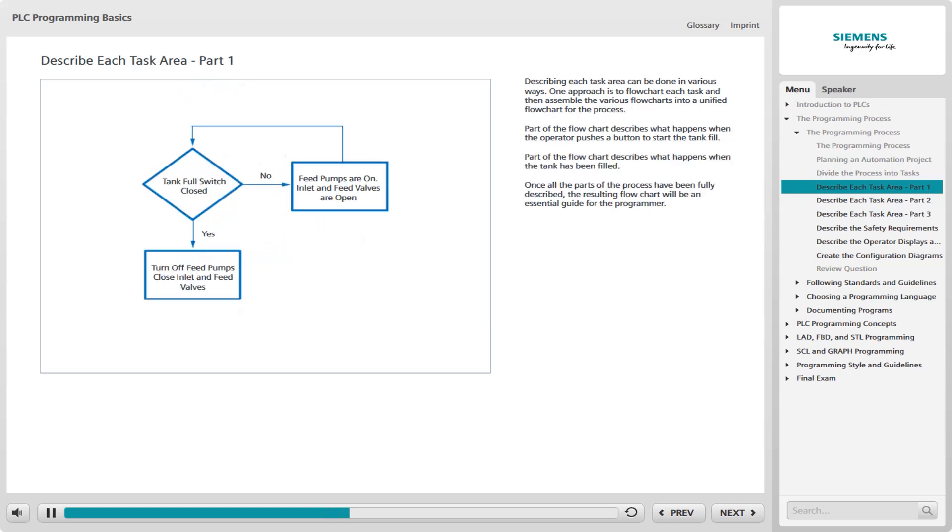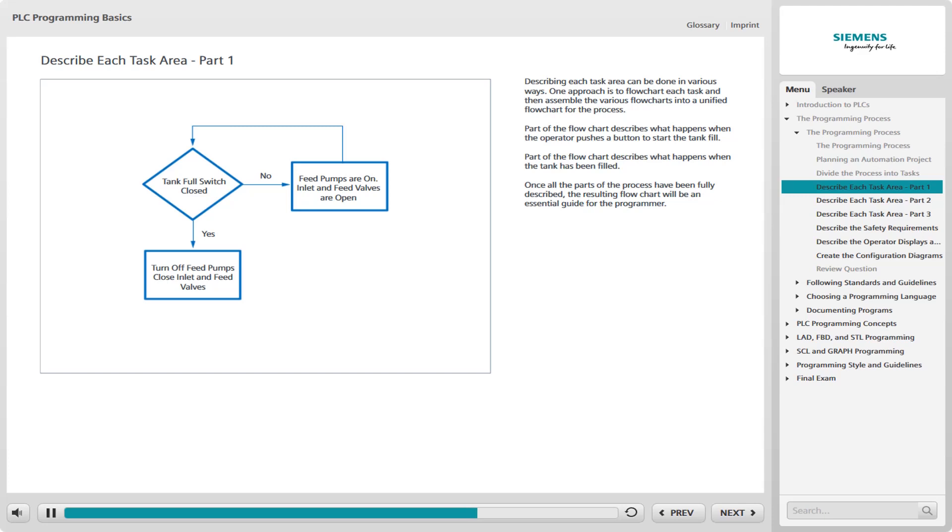Another part of the flowchart describes what happens when the tank has been filled. As the accompanying graphic shows, when the tank full limit switch closes, the feed pumps are turned off and the inlet and feed valves are closed. Keep in mind that there may be other conditions that cause this to occur as well. For example, there may be a manual push button that an operator can press to shut off the flow to the tank, and this would also be part of the flowchart.